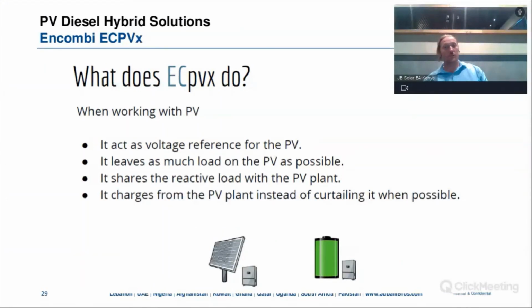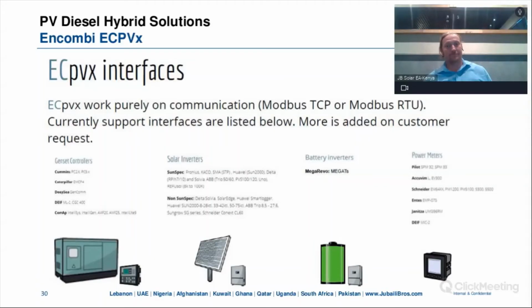And when it works with the solar, the ECPVX acts as a voltage reference for the PV. So that means even if the grid fails, your grid-tied inverters can continue to produce. It maximizes the PV consumption because we know this is the free energy from the sun. So this is what you want to consume the most of, so it will maximize the load on the PV. It will also share the reactive load with the PV plant to maintain the power quality. And if you have batteries, instead of reducing the PV output, it will charge the batteries with the PV. So it can do all of that.